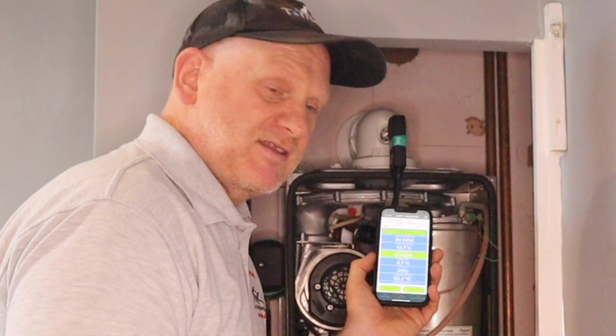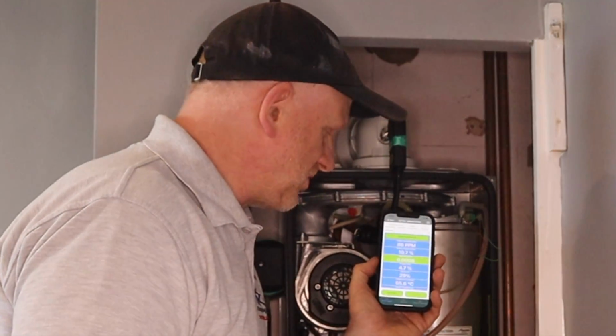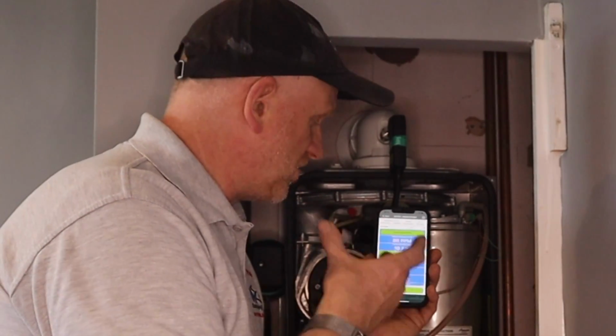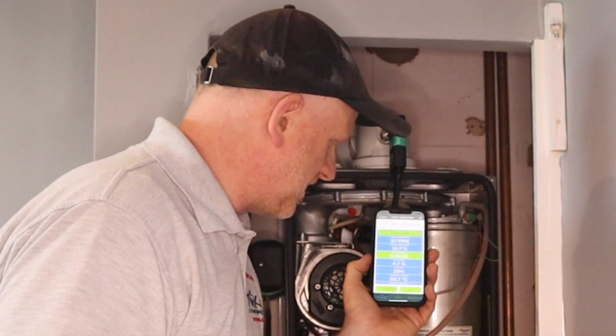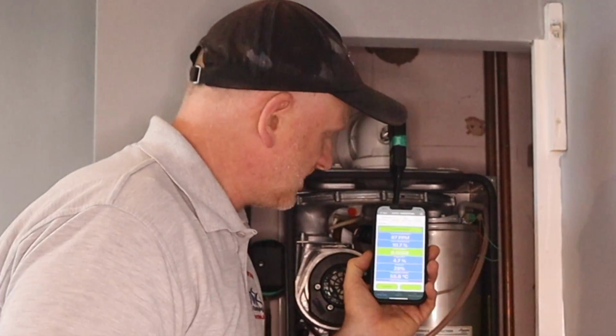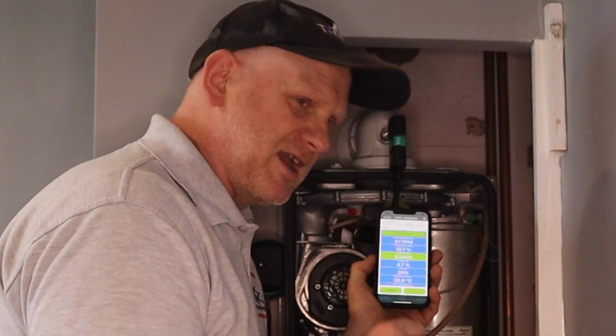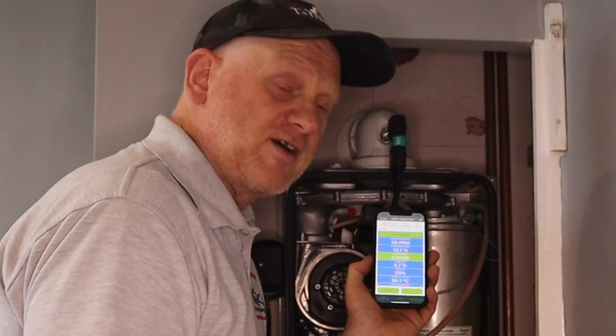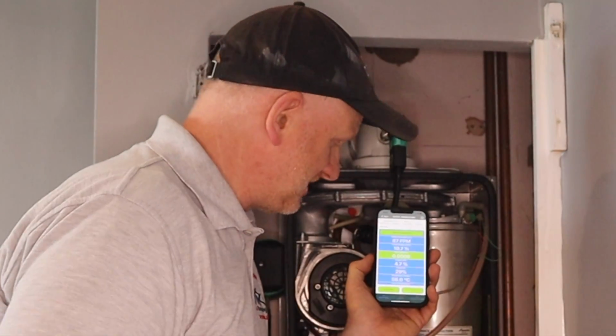Every time I'm flicking it back to minimum now, it's kind of changing it all the time. So I've just been playing around with it for a little bit, but at least now I've not got those really horrendous CO figures of 1,100 and whatever they were yesterday, and we seem to be modulating quite nice. Well, it's in high fire, but it seems to be working quite nicely now in high fire. It's low fire I'm getting a bit of a problem with, so I'm going to play around with it a little bit more and see what I get at low fire. But it's looking better than it did yesterday.